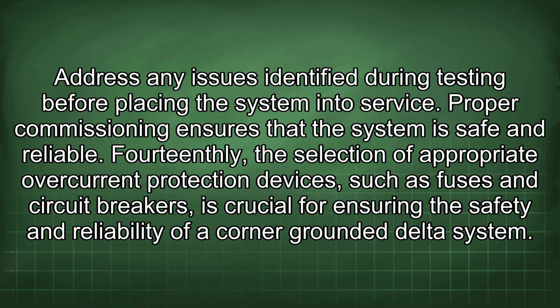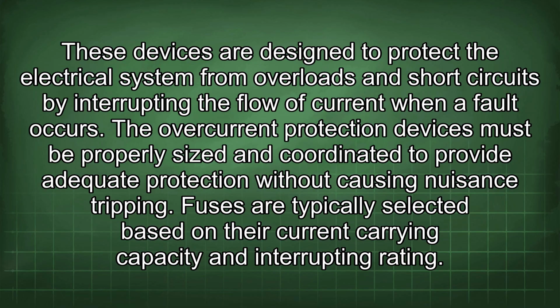14thly, the selection of appropriate overcurrent protection devices, such as fuses and circuit breakers, is crucial for ensuring the safety and reliability of a corner-grounded delta system. These devices are designed to protect the electrical system from overloads and short circuits by interrupting the flow of current when a fault occurs. The overcurrent protection devices must be properly sized and coordinated to provide adequate protection without causing nuisance tripping.